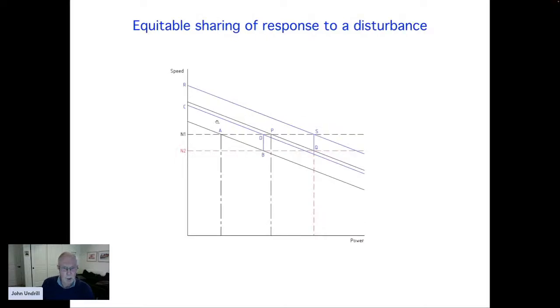If I have 2 generators on, for example, and at some moment the first generator is operating at a power level A, and the second generator is operating at a power level P, and everything's sitting steady and running very smoothly, and then I experience a sudden increase in load, perhaps somebody turns on a large compressor in a liquefied natural gas facility somewhere, and I have a large increase in load, then the speed is going to have to go down.